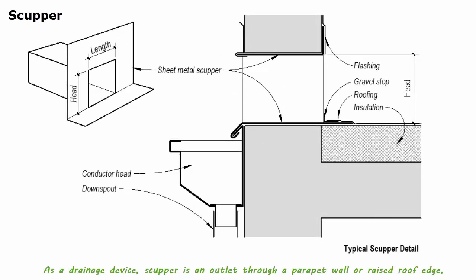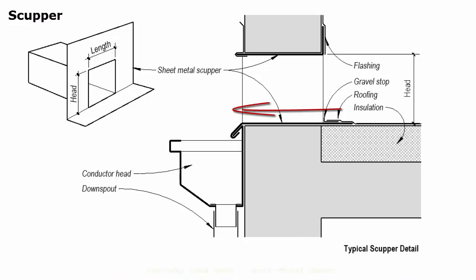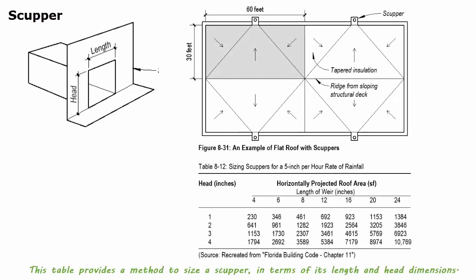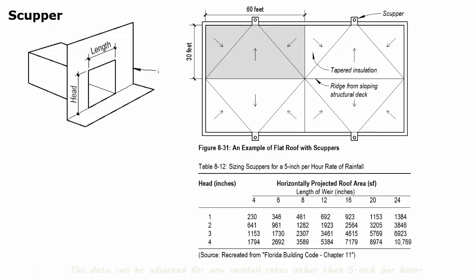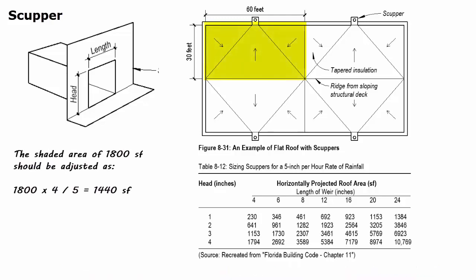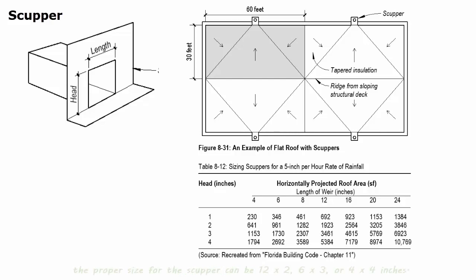As a drainage device, a scupper is an outlet through a parapet wall or raised roof edge, typically lined with a sheet metal sleeve, allowing water runoff to leave the roof through a downspout attached to the surface of the building. This table provides a method to size the scupper in terms of its length and head dimensions, based on a 5-inch-per-hour rainfall rate; the data can be adjusted for any other rainfall rate. For example, if the building is in an area with a 4-inch-per-hour rainfall rate, the shaded area of 1,800 square feet is adjusted to 1,800 times 4 divided by 5, which equals 1,440 square feet. According to the table, the proper scupper size can be 12 by 2, 6 by 3, or 4 by 4 inches.